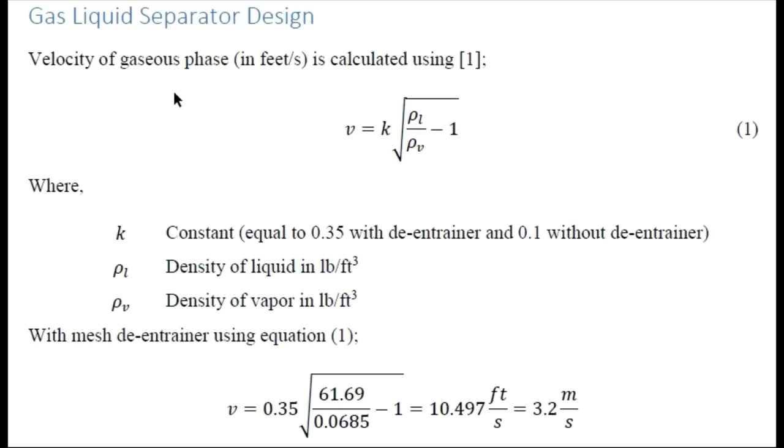First of all we need to find the velocity of the gas stream. We will be using this equation, equation number 1, which includes the densities of liquid and vapor phase and this constant value K. Here you can clearly see that K value is 0.35 for de-entrainer, if we are using some separator at the top to avoid the carry over of moisture, and it is 0.1 if we are not using any de-entrainer. By substituting the values in equation 1 we can find the vapor velocity that is 10.497 feet per second in this case, and we can convert it into meter per second as well.